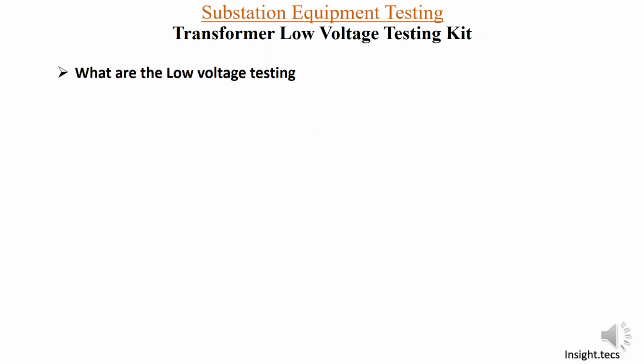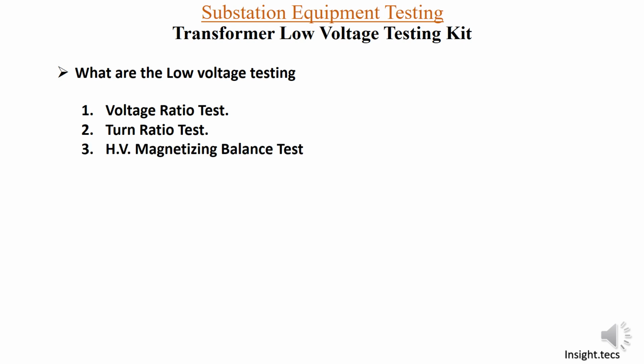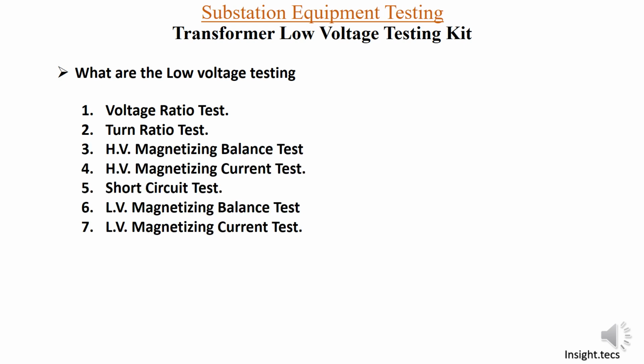We have already seen various kinds of low voltage testing: voltage ratio, turns ratio, HV balance, HV magnetizing current, short circuit, LV magnetizing balance test, vector group and winding resistance. So we have already covered a few low voltage tests from this list, and today we are going to see HV magnetizing current.